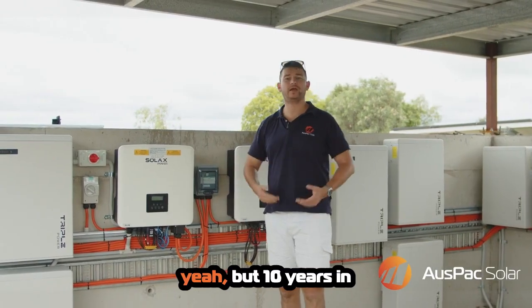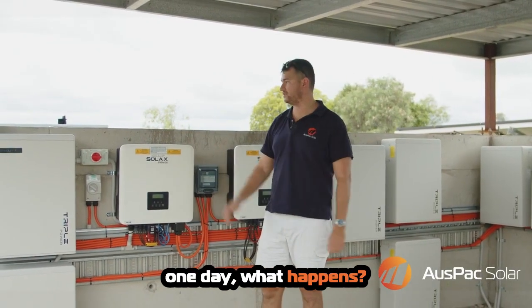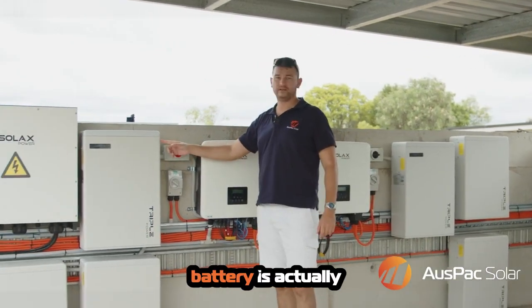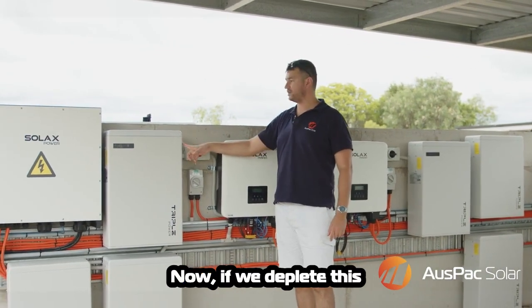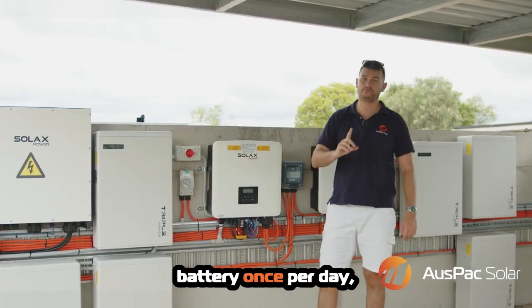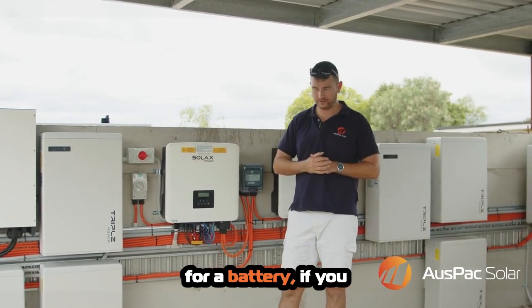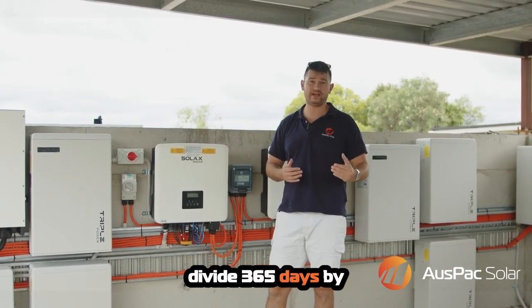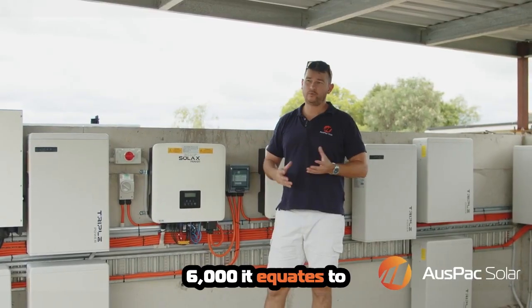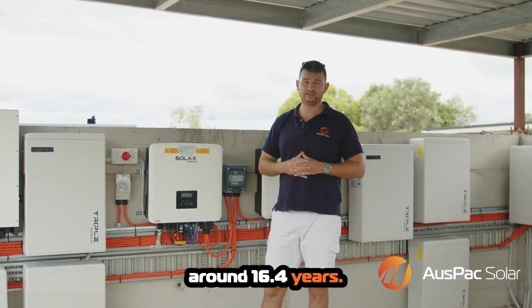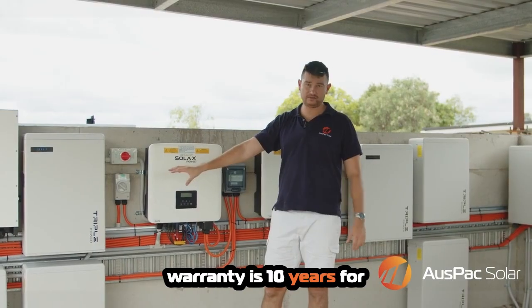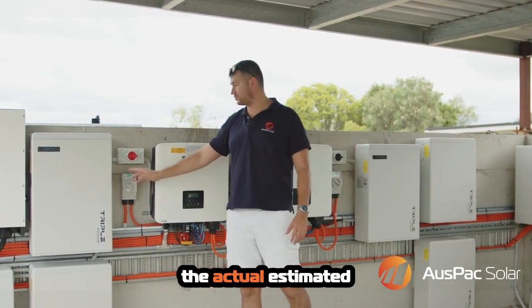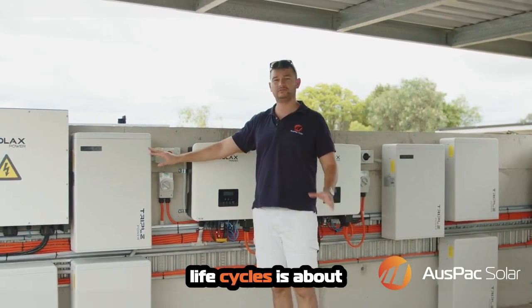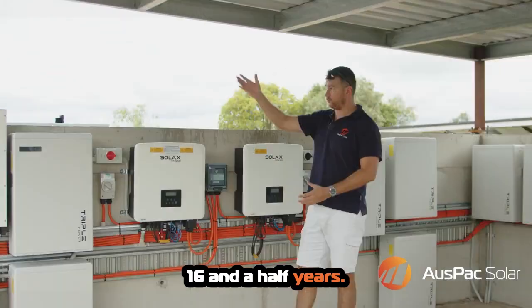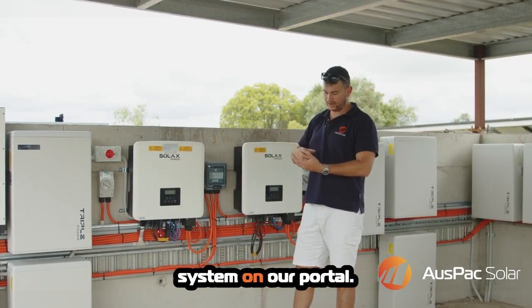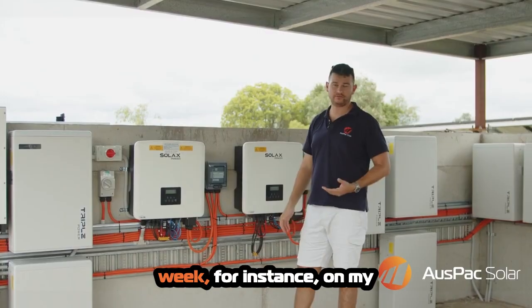A lot of people ask me, yeah, but 10 years and 1 day, what happens then? The life cycle of this battery is actually 6,000 cycles. Now, if we deplete this battery once per day, which is the standard for a battery, if you divide 365 days by 6,000, it equates to around 16.4 years. So even though the warranty is 10 years for each of these batteries, the actual estimated life cycle is about 16.5 years.